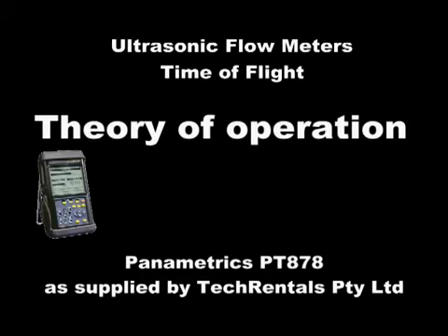The Panametrics PT878 uses a technique called time of flight. This technique will be specifically covered here. There are also other instruments which utilise the Doppler effect to measure flow using ultrasonics.